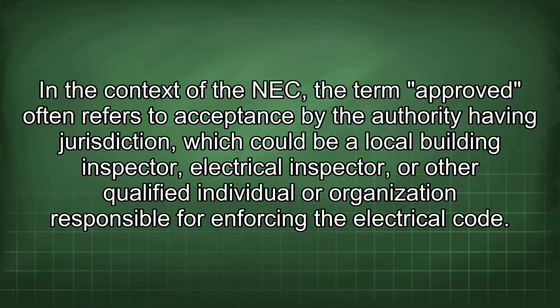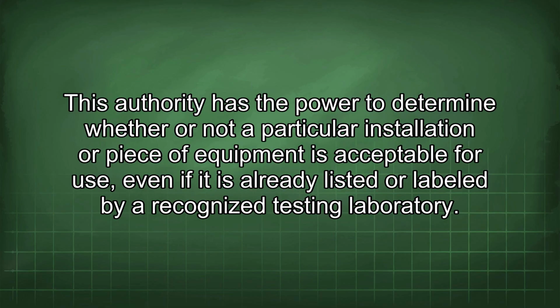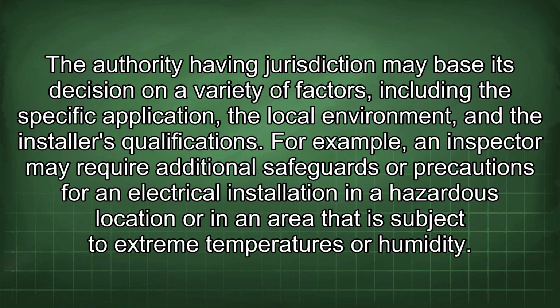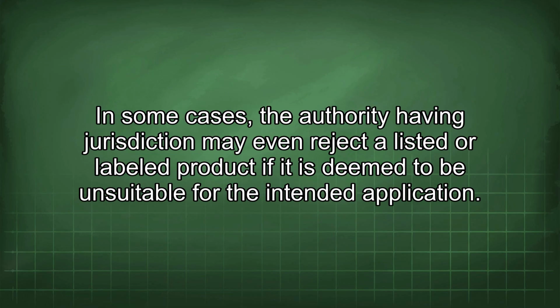In the context of the NEC, the term approved often refers to acceptance by the authority having jurisdiction, which could be a local building inspector, electrical inspector, or other qualified individual or organization responsible for enforcing the electrical code. This authority has the power to determine whether or not a particular installation or piece of equipment is acceptable for use, even if it is already listed or labeled by a recognized testing laboratory. The authority having jurisdiction may base its decision on a variety of factors, including the specific application, the local environment, and the installer's qualifications. For example, an inspector may require additional safeguards or precautions for an electrical installation in a hazardous location or in an area that is subject to extreme temperatures or humidity. In some cases, the authority having jurisdiction may even reject a listed or labeled product if it is deemed to be unsuitable for the intended application.